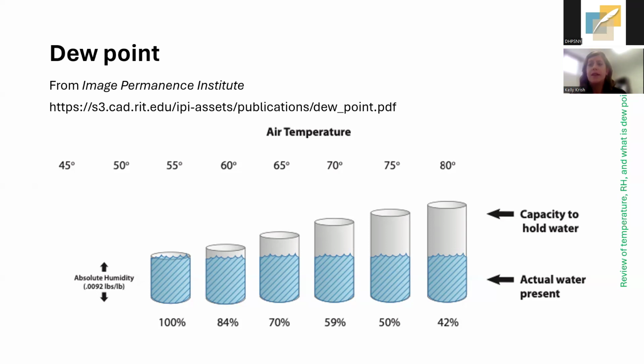So hopefully that makes sense in terms of conservation heating, or sometimes the emergency recommendations, if people can't dehumidify and their relative humidity starts to increase, sometimes people recommend increasing the temperature to try to bring that back down. So that's where this is coming from. They're not actually removing any moisture, but they're making that container big enough that the relative humidity is going down. So I think the useful thing to keep in mind here, and we'll see it in another format on the next slide, is that as temperature increases, the relative humidity goes down, and vice versa. And the other thing is that in this example, the dew point isn't changing. There are only so many ways that we can actually affect the dew point, and you'll see that throughout the webinar.